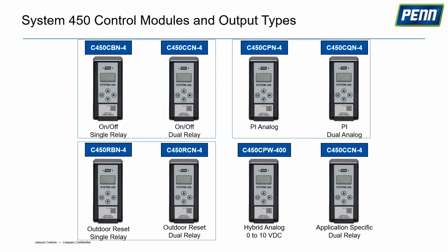The other one here is the C450 CCN-4. This is what we call an application-specific controller, and it does have two relays on board, but again, you can add additional relays by adding expansion modules. This is specifically designed for use with walk-in coolers and freezers and large display cases that have remote condensers. So in addition to temperature control, it will also do high-low speed fan control, it will do defrost control, and it will do pump down control as well.